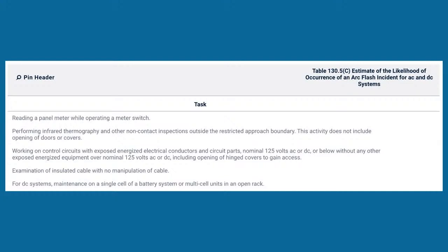All right, now we looked at this two weeks ago and we looked at table 130.5C as part of abnormal conditions. And this is where you get into the estimate of the likelihood of occurrence again. There's that same terminology of an arc flash incident for AC and DC systems. And then you come in and you've got these different tasks. I'll give you an example of one here. It says, the second one, performing infrared thermography and other non-contact inspections outside of the restricted approach boundary. This activity does not include opening of doors and covers.